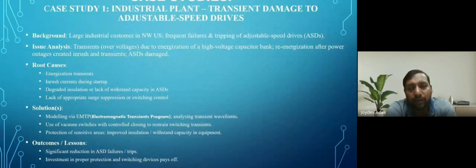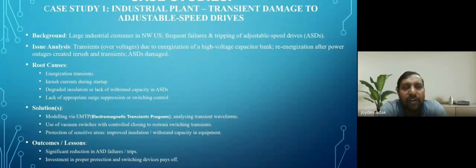So now, before going to the recommendation, we'll discuss different case studies. First, non-DVC case studies. After that, we'll discuss DVC case studies. First, this is the common case study of ASDs, adjustable speed drives, similar to variable frequency drives (VFD). During transients and capacitor bank insertion, transients occur, and due to these transients and the starting of the drives, several times the drives get damaged, or it costs much.